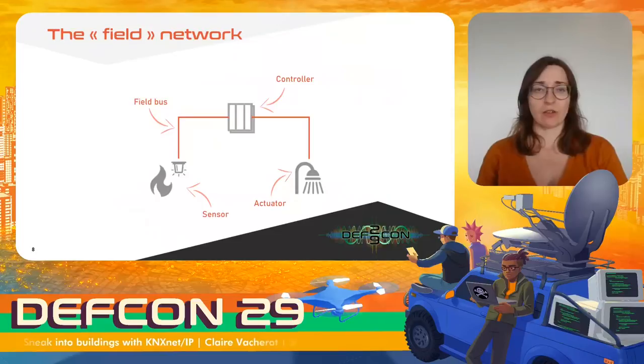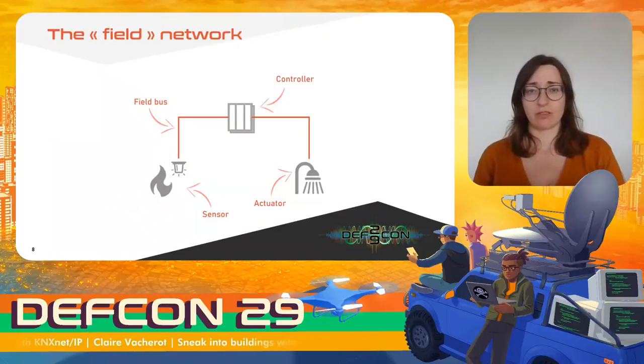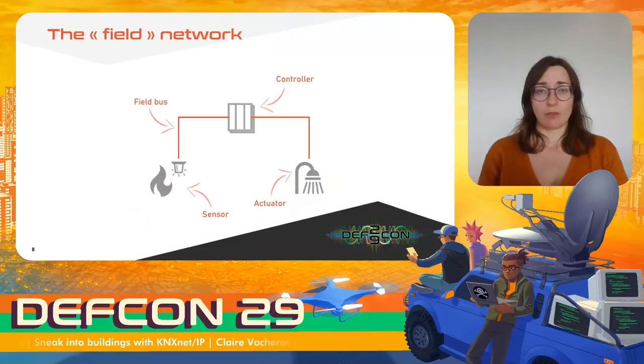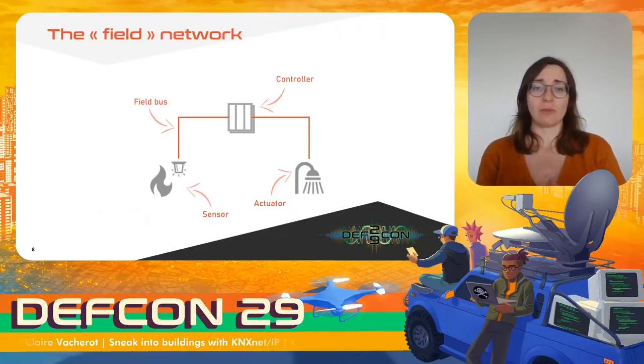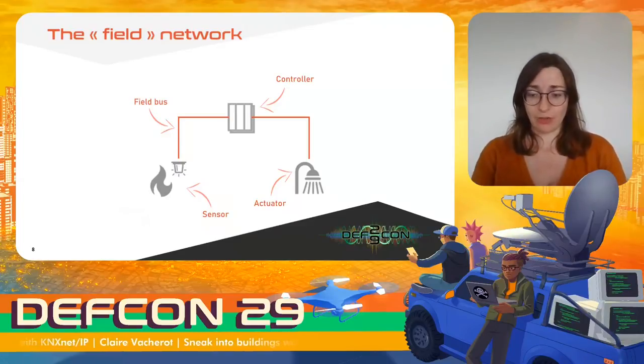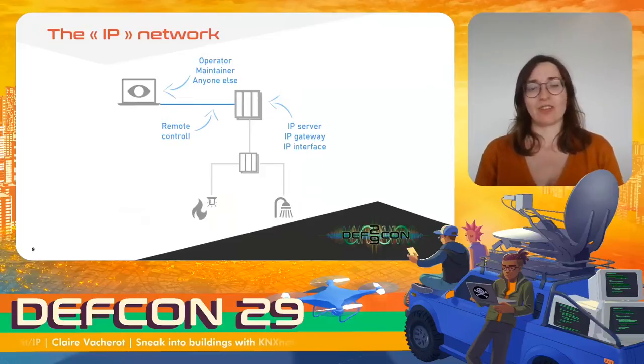Let's take a closer look at this technically. In BMS, the main part is the field part, where the actual components are. We often find three types of components: sensors, actuators, and controllers. These devices communicate with each other using fieldbus protocols, usually twisted pairs or radio frequencies. This part can work standalone, and in fact before, it was the only part. But then the field part got connected to the IP network.